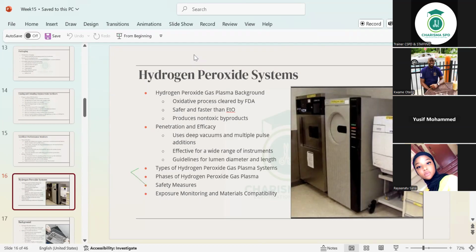All right. So the hydrogen peroxide, as they just said, is safer and faster than the ethylene oxide, which is good news. For me, it's very good news, right? So this system uses hydrogen peroxide as the sterilant, and the process that it uses is the oxidative process. It has rapid cycles as compared to the ETO, and the byproducts are not toxic. The byproducts of hydrogen peroxide are not toxic, okay? It's a very highly effective sterilant that sterilizes by oxidation of key cellular components.